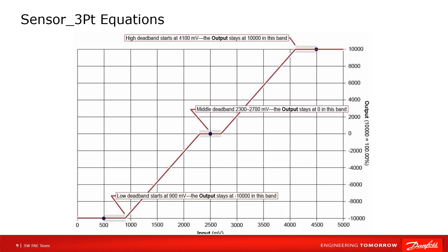Compare with previous trace. There are three dead band areas after setting dead band to 1000. When input is between 2300 and 2700, output is 0. When input is below 900, output is minus 10000. And when input is above 4100, output is 10000.